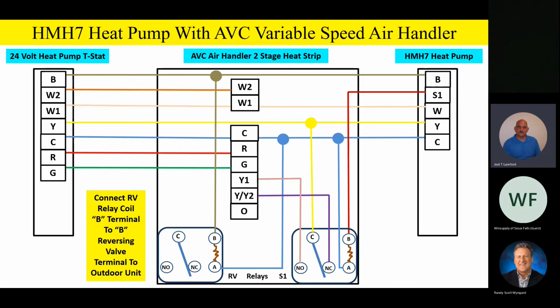When this thing goes into the heating mode of operation on the heat pump, it's going to energize that RV relay coil, and it's going to switch that relay. Now, the only purpose for this RV relay, by the way, is that during compressor operation, we're going to take 24 volts from the Y terminal and go to the common terminal for the switching contacts on the RV relay. The normally closed contact on the RV relay is going to go up to the O terminal.